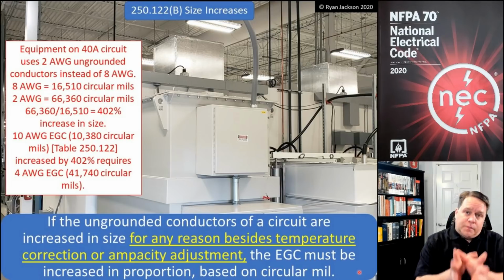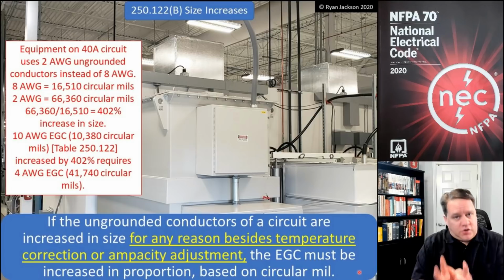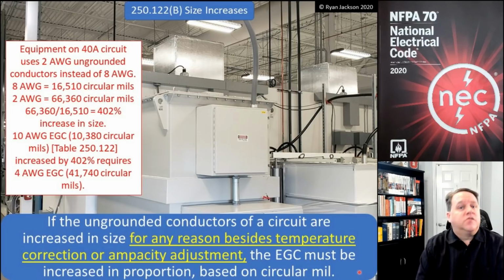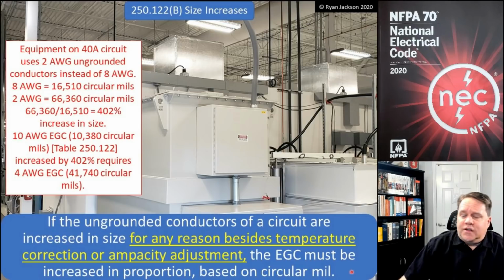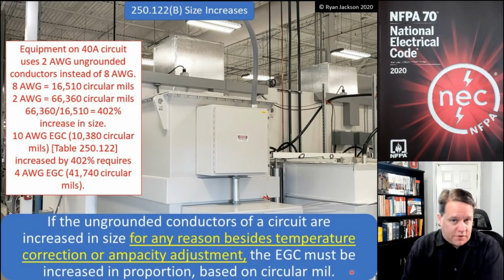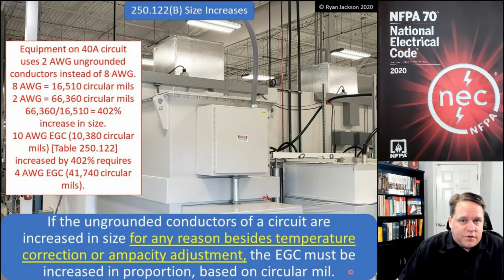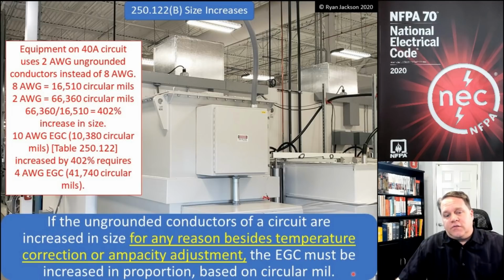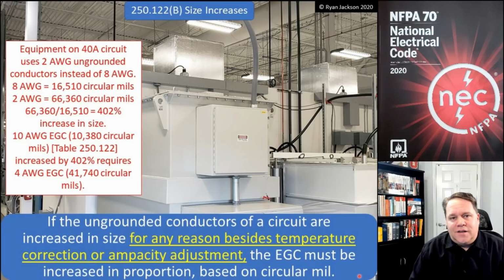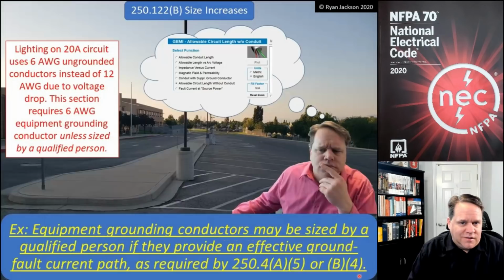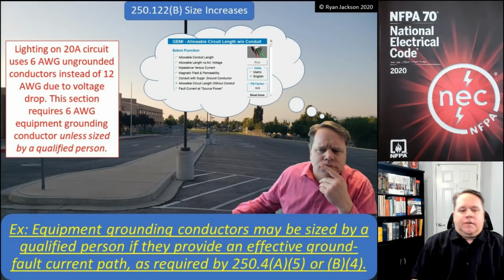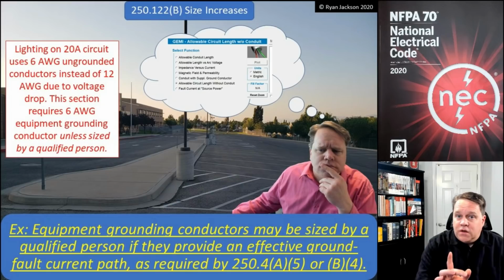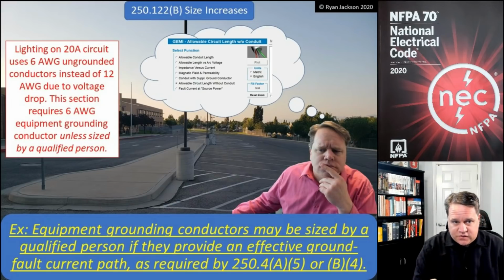We make changes, the public reviews it, the public provides comments, and then we change the code based on those comments. At the end of the day, what they ended up doing is saying, look, we have no idea how to fix 250.122(B) and make it applicable for everything, because it might not even be possible. So we're going to keep sizing the things the way we always have, and then we're going to add this very interesting exception. It says, look, equipment grounding conductors, now this is only for size increases. This is just 250.122(B). It's not the entire section.